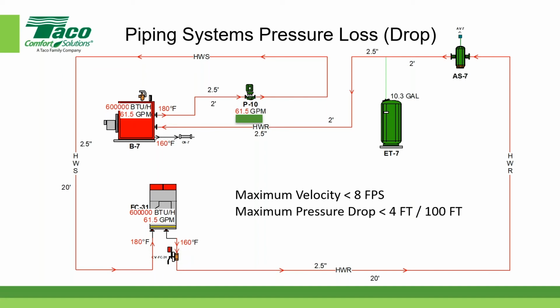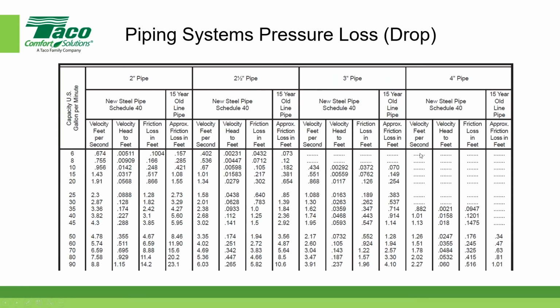So then I went into a chart similar to the one I showed you a moment ago, and I said, okay, I've got just over 60 gallons per minute. So I go over here to a chart and get my highlighter. Here I have 60 gallons per minute, and I want a velocity of less than 8 feet per second. The velocity for the 2-inch pipe up here is 5.74, but the pressure drop per 100 feet is around 6.59. And I wanted a maximum pressure drop of 4 feet per 100 feet. So 2-inch pipe is not going to work in my case.